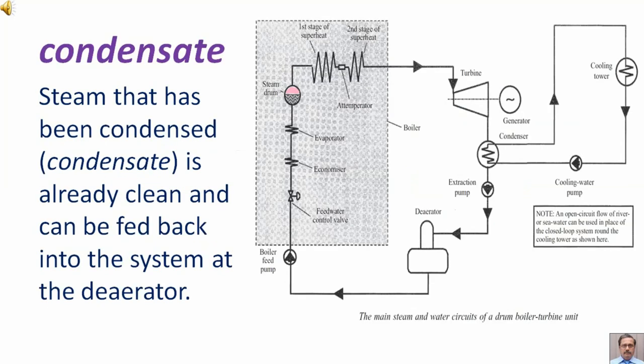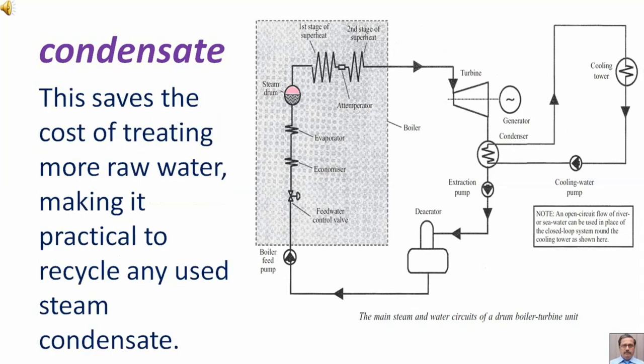Condensate. Steam that has been condensed, that is condensate, is already clean and can be fed back into the system at the deaerator. This saves the cost of treating more raw water, making it practical to recycle any used steam condensate.